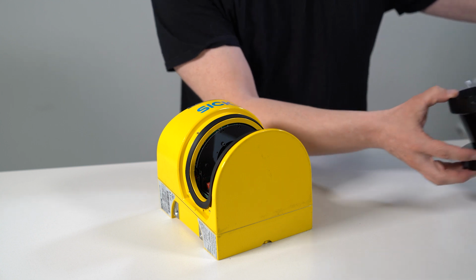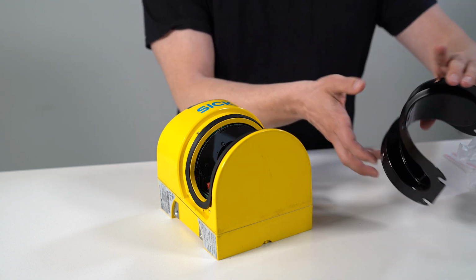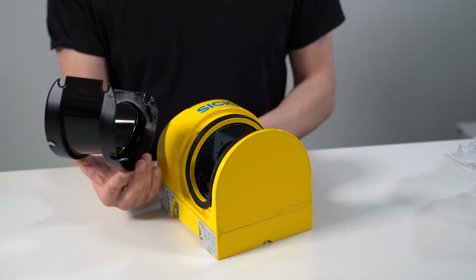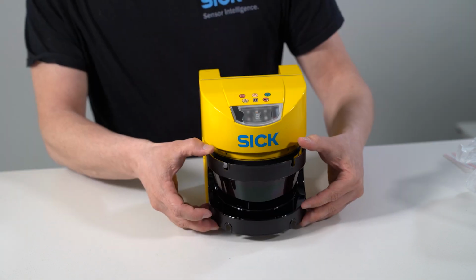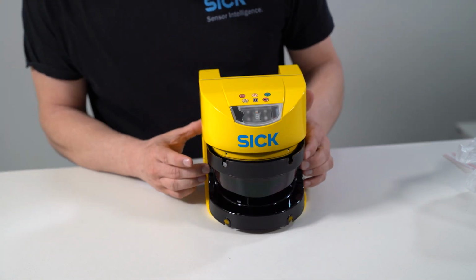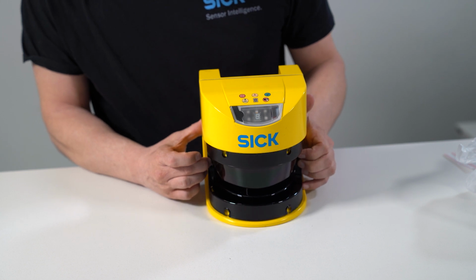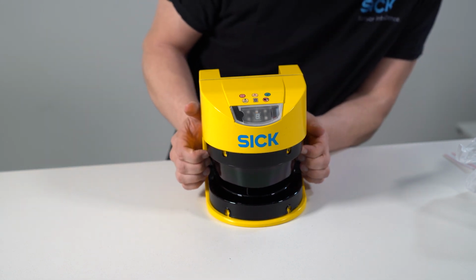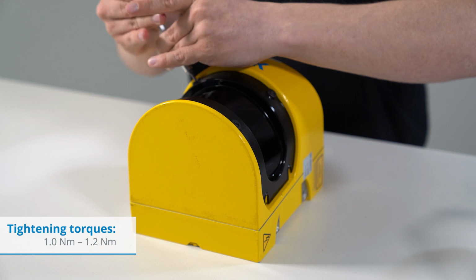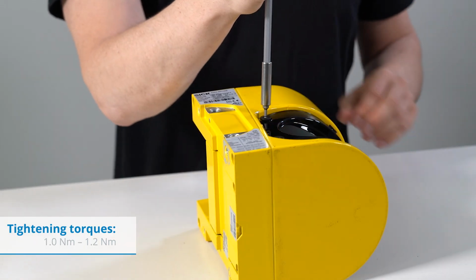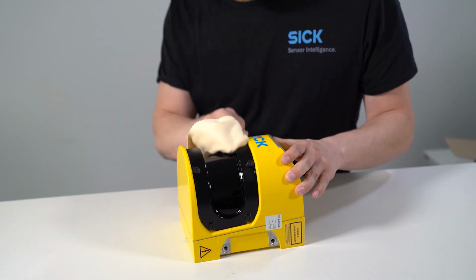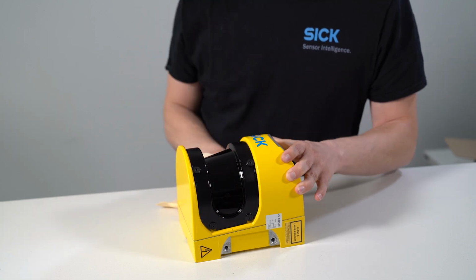Take the new optics cover out of the packaging and remove the seal's protective cap. Remove any packaging residue if necessary. Carefully place the optics cover on the seal and insert the 4 front screws with the washers. Press the front screen onto the scanner and tighten the screws. When this is done, insert and tighten the remaining screws. Make sure that the optics cover is clear of dirt and damage.